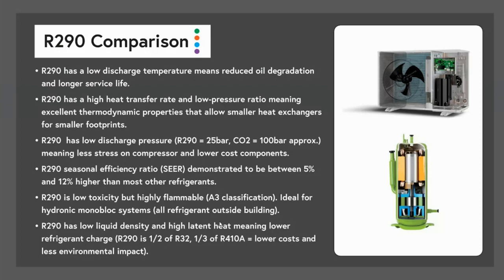The last point there is that R290 has a low liquid density and a high latent heat, meaning a lower refrigerant charge. Just to make a comparison again, compared to R32, it uses about half of the refrigerant, and about a third of the refrigerant of an R410A. So what does that mean? It means lower refrigerant costs, so lower costs for the unit and lower long-term costs, and less environmental impact, just because of the amount of refrigerant that's actually being used in the appliances.